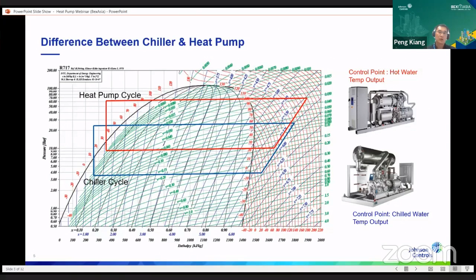That's the basic difference - some people get confused between chillers and heat pumps. A chiller is for creating chilled water as its control point, while a heat pump creates hot water on the high side of the heat pump.